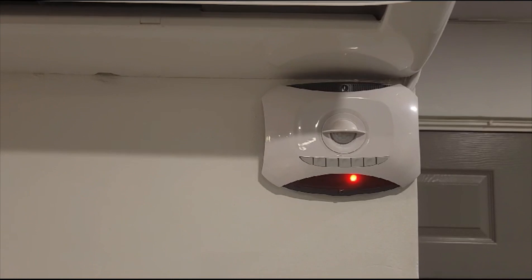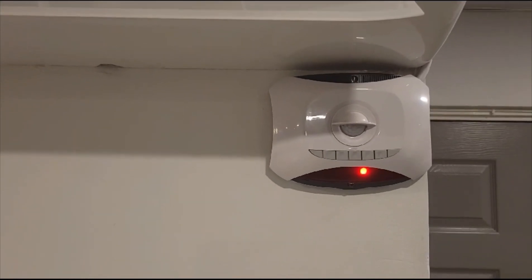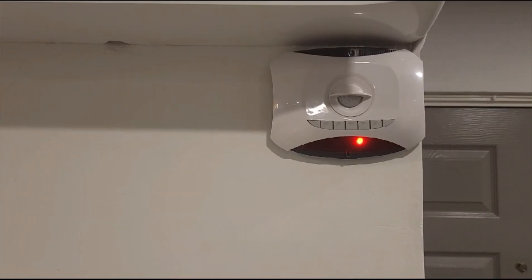The only way that you would actually rectify this is to close the door. You can see the red light is on — this means that the balcony door is not closed, so the unit will shut down in five minutes. That's just a way for troubleshooting.